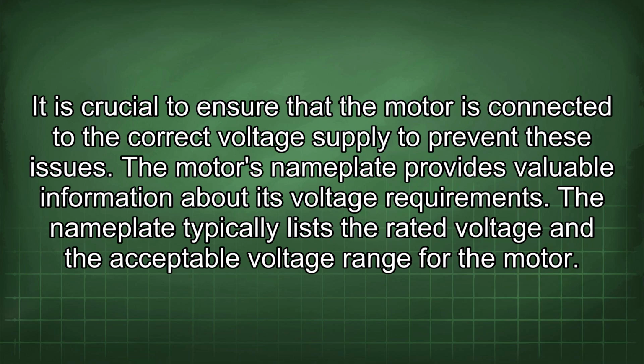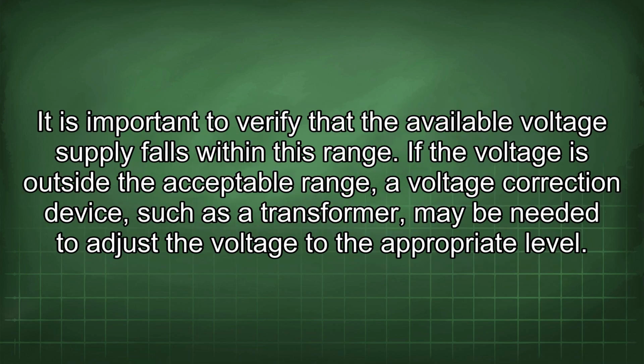The motor's nameplate provides valuable information about its voltage requirements. The nameplate typically lists the rated voltage and the acceptable voltage range for the motor. It is important to verify that the available voltage supply falls within this range. If the voltage is outside the acceptable range, a voltage correction device, such as a transformer, may be needed to adjust the voltage to the appropriate level.